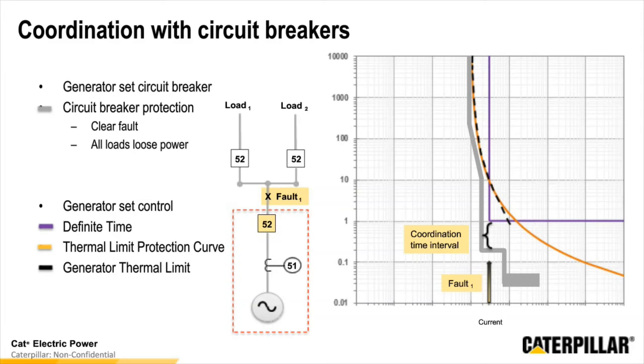So as we see here, if the fault is occurring just directly outside of the generator breaker, and in this case we're at roughly 300% of the rated current, then we are going to be tripping the breaker at roughly 0.2 of a second versus the full second that we had set for the protective relay.